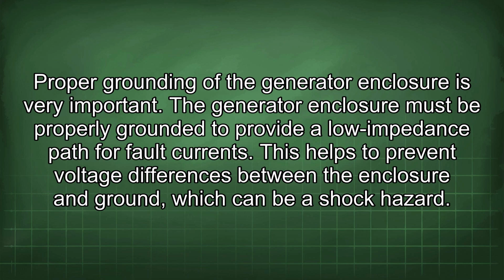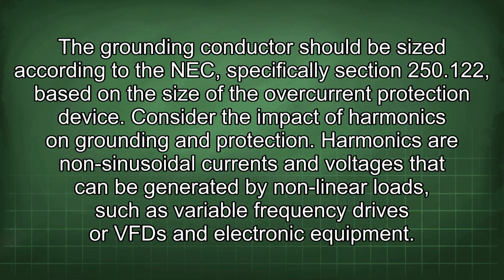Proper grounding of the generator enclosure is very important. The generator enclosure must be properly grounded to provide a low impedance path for fault currents. This helps to prevent voltage differences between the enclosure and ground, which can be a shock hazard. The grounding conductor should be sized according to the NEC, specifically section 250.122, based on the size of the overcurrent protection device.